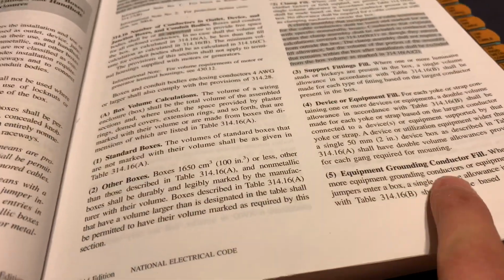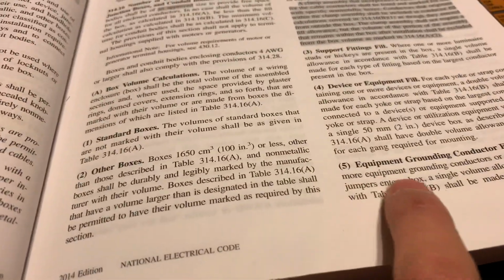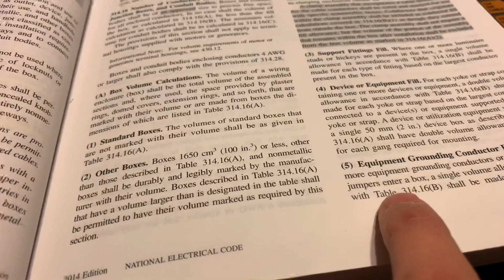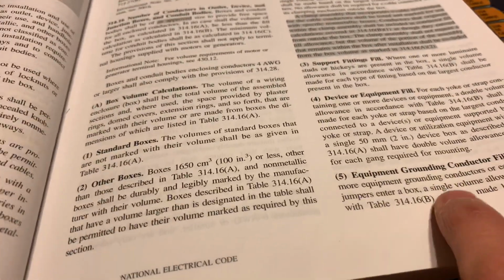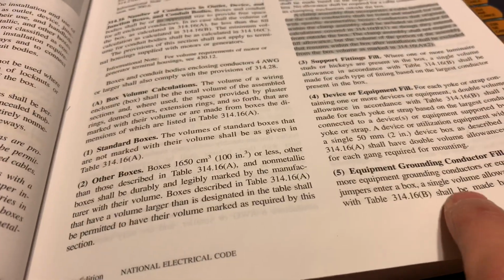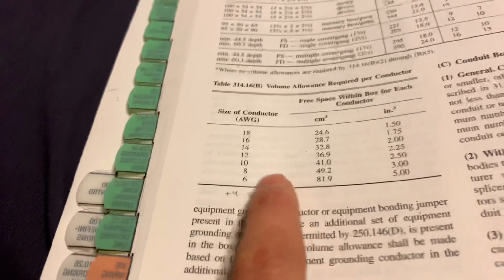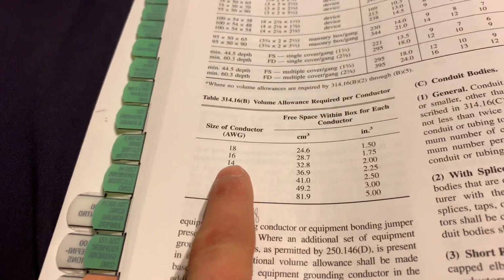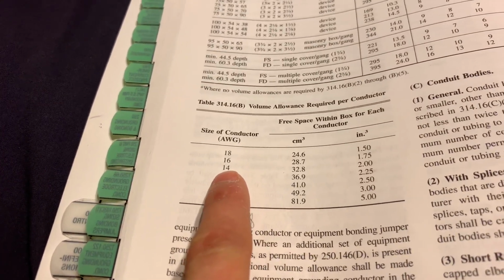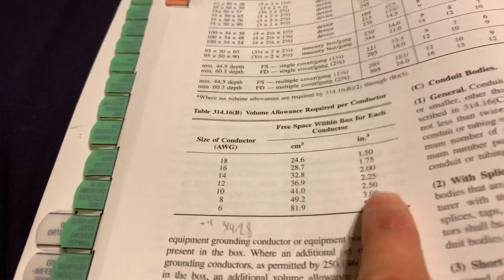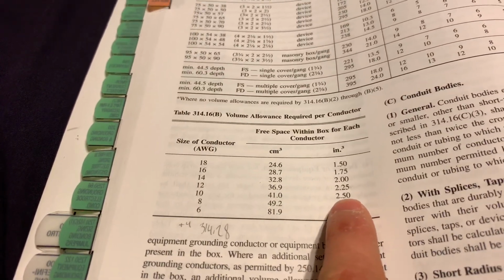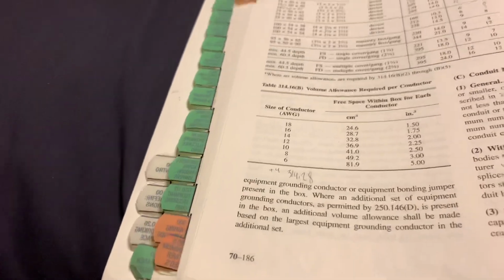Equipment ground right here. One or more equipment grounding connectors or equipment bonding jumpers enter a single box. A single volume allowance in accordance with this shall be made based on the largest ground. So basically, if you have a number 10 ground and then, say, three number 14s and a 10 wire, the ground is going to count as 2.5 because that's the largest ground in the box. There's a lot of stuff to go over, just trying to give you some basics here.